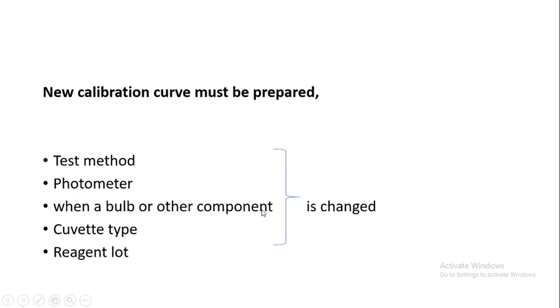A new calibration graph should be prepared whenever test method, photometer or colorimeter, bulb or component, cuvette type, or reagent lot is changed.